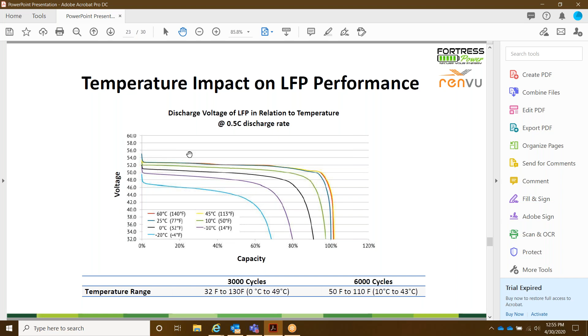Next, I want to look at cycle life versus depth of discharge. So as I mentioned, we recommend an 80% depth of discharge for the 6,000 cycles. If you were to cycle that one time a day, that's around 12 to 15 years. The reason why I put this chart here is because some of their batteries claim to have 12,000, 13,000 cycles. But what they're not telling you is that this depth of discharge is only at a 50% depth of discharge. So if you have a 10 kilowatt hour battery, you're only able to get 5 kilowatt hours out of that. So depending on the application of the project, whether it's a time of use rate, maybe 80% or 70% might be the way to go.